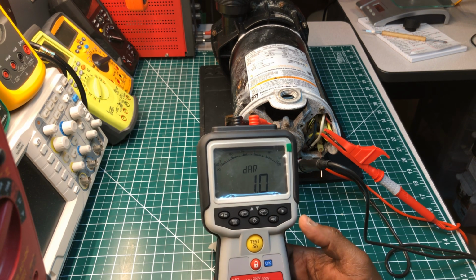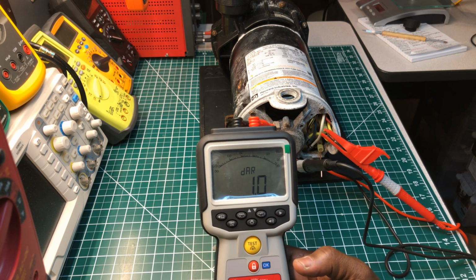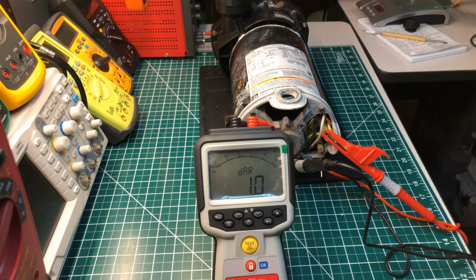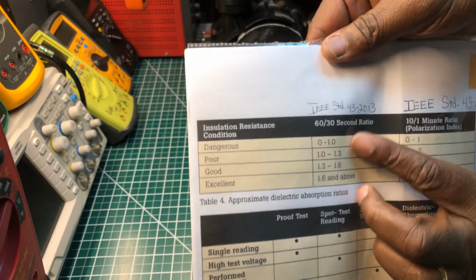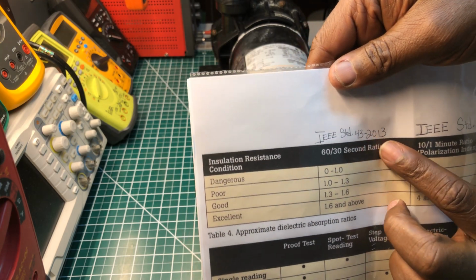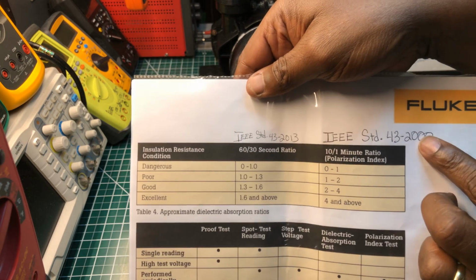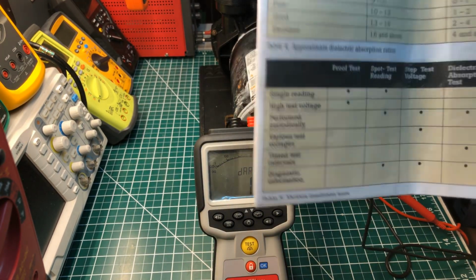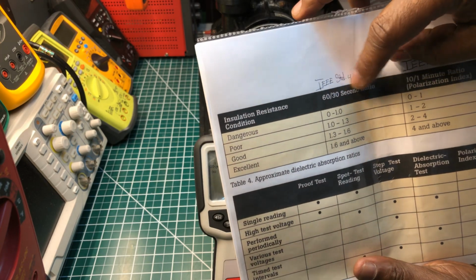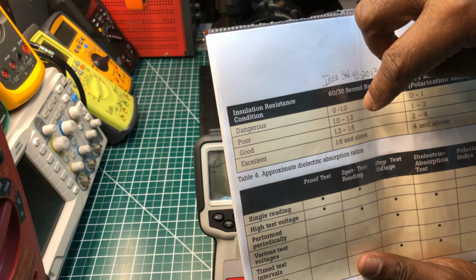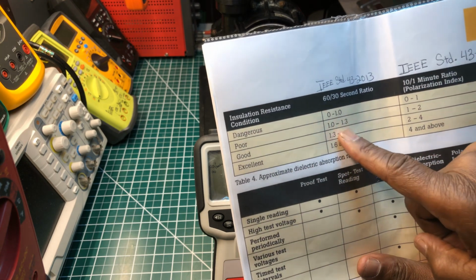Okay, so it's saying 1.0. That's the DAR test. According to this IEEE standard 43-2000, a DAR test, if it's 1.0, that's saying that it's dangerous. If you can see this right here, that's what I'm going by, the IEEE standard. The MEGGER's giving us on a DAR test, which would be right here, the 30-second to 60-second ratio, and that would be dangerous right here.